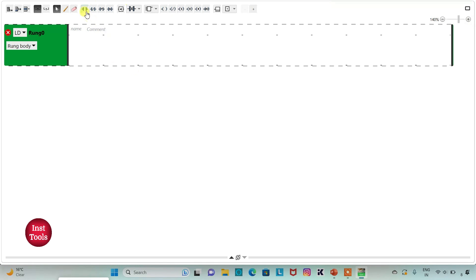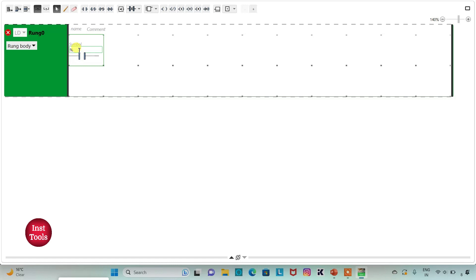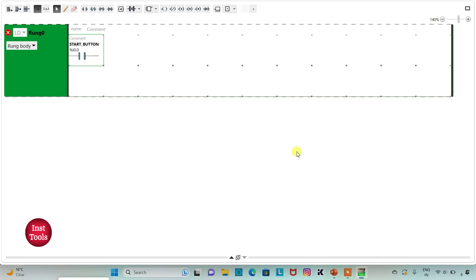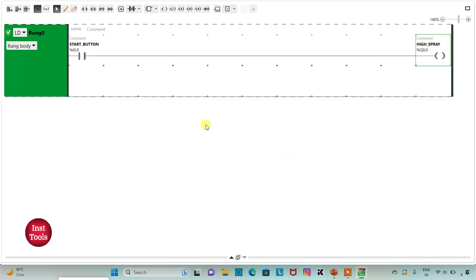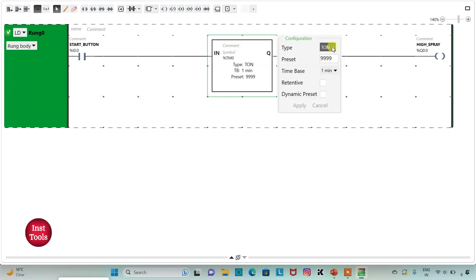First I will insert a normally open contact and assign the address I0.0, adding the symbol 'high spray'. High spray should be for 15 seconds, so I will insert a functional block timer of type TP. I will change the time base to 1 second and set the preset value to 15, then click apply.